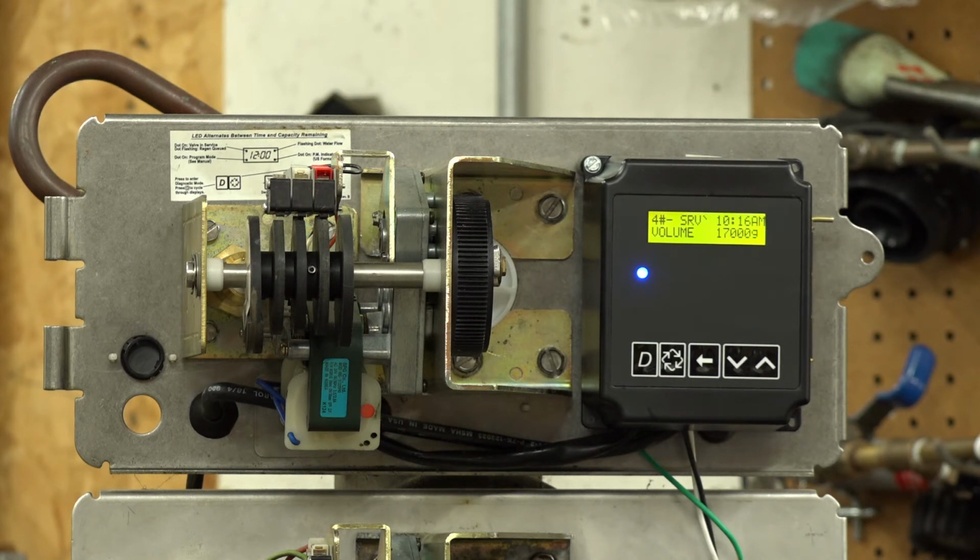Now, one thing to look at, and this is on both the Fleck 2900 and the Fleck 3900, is that your lower piston cap is colored. The black cap means no hard water bypass. If this cap is white, it means there's hard water bypass during regeneration. So when this piston moves in during regeneration, if you have a black cap, no water is allowed to your outlet. If this cap is white, water is allowed to your outlet even during regeneration. In this case, it's a black cap. No water is allowed to your outlet during regeneration.